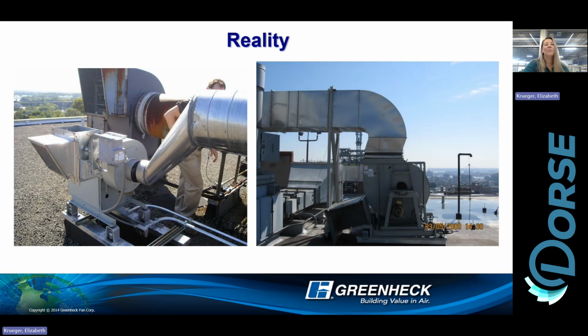If you can, design a system with the nice three wheel diameters of straight ducting, and the same goes for the discharge side. So this fan, and I know Chris kind of hit on this in the beginning. Yep, I knew you wanted to talk about this one. So Chris talked about choosing the right direction, number one, rotation and discharge. So the second fan really highlights choosing that. Right now with the airflow, the second fan's discharge, that air wants to continue in that scroll shape. It wants to continue flowing in a circle. And instead of allowing the air to continue in that direction, boom, they're breaking the back of the fan.